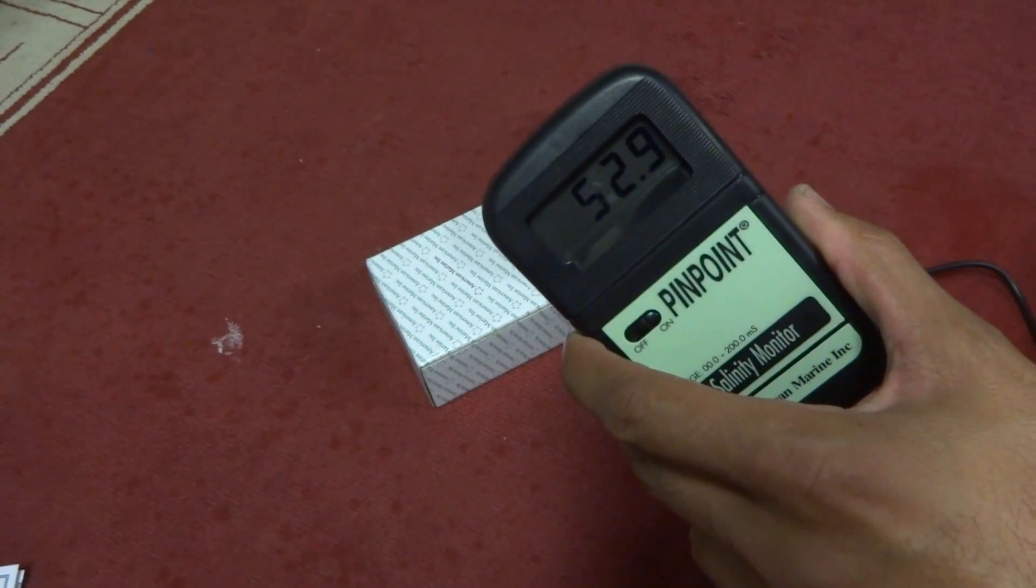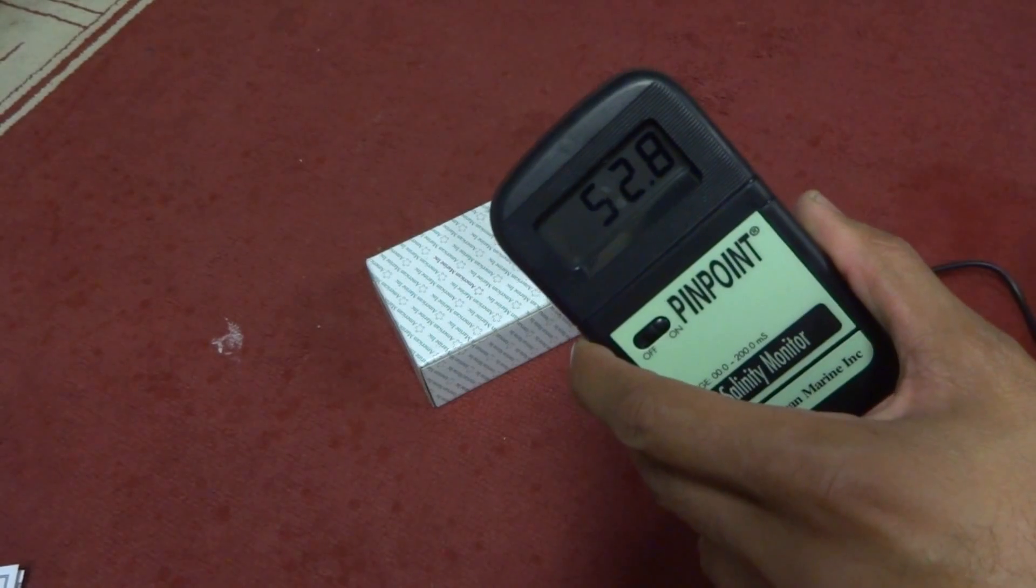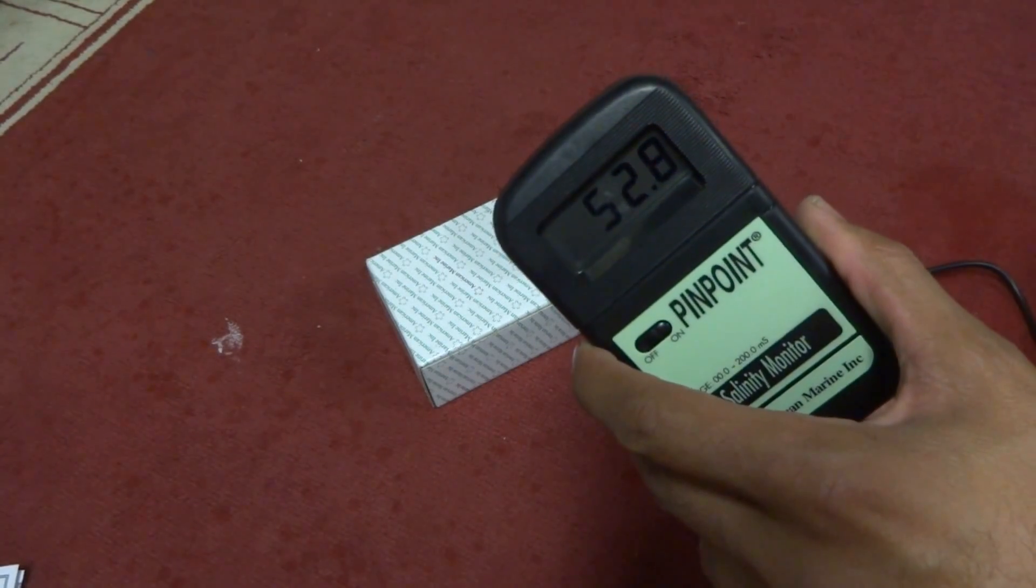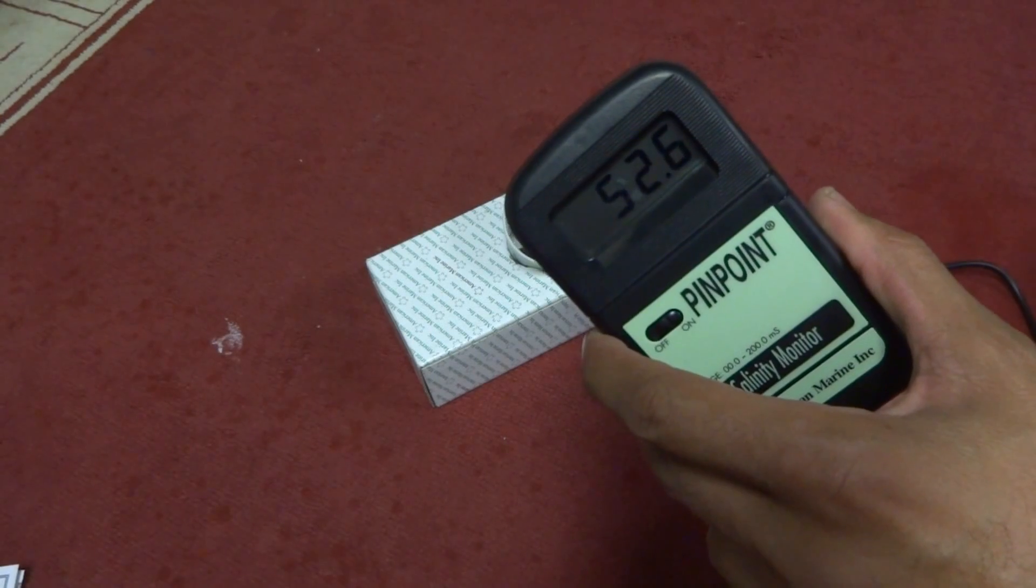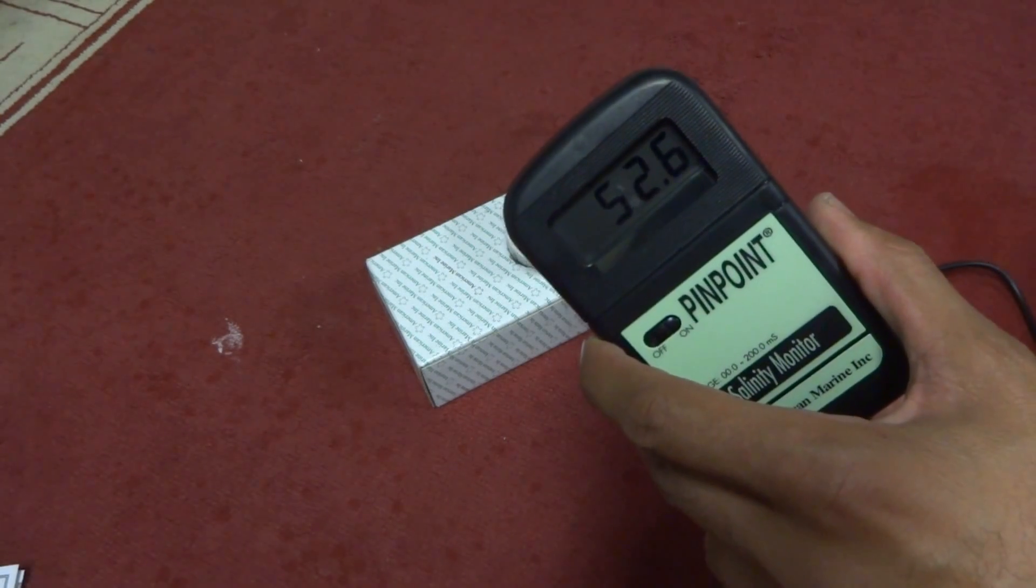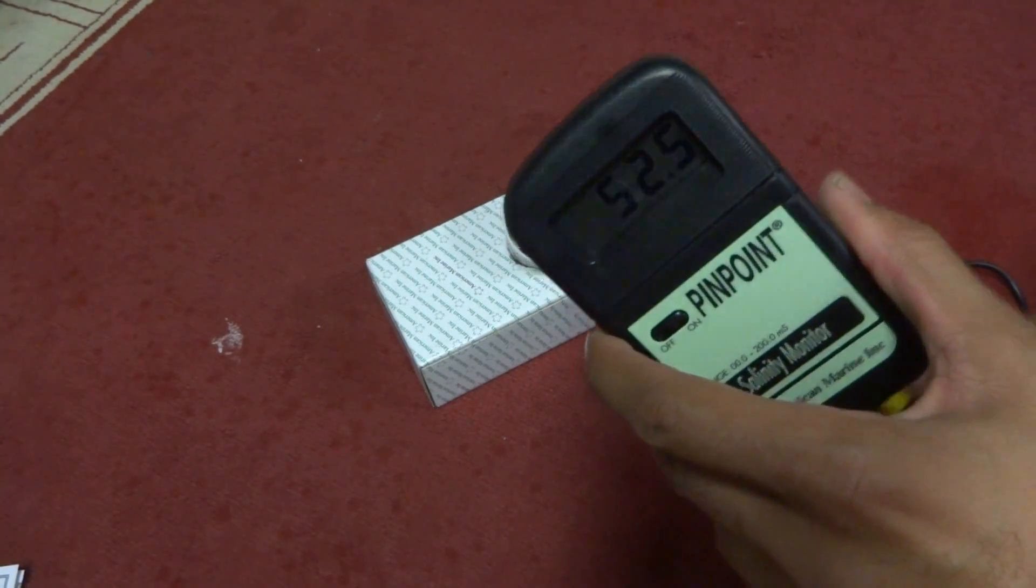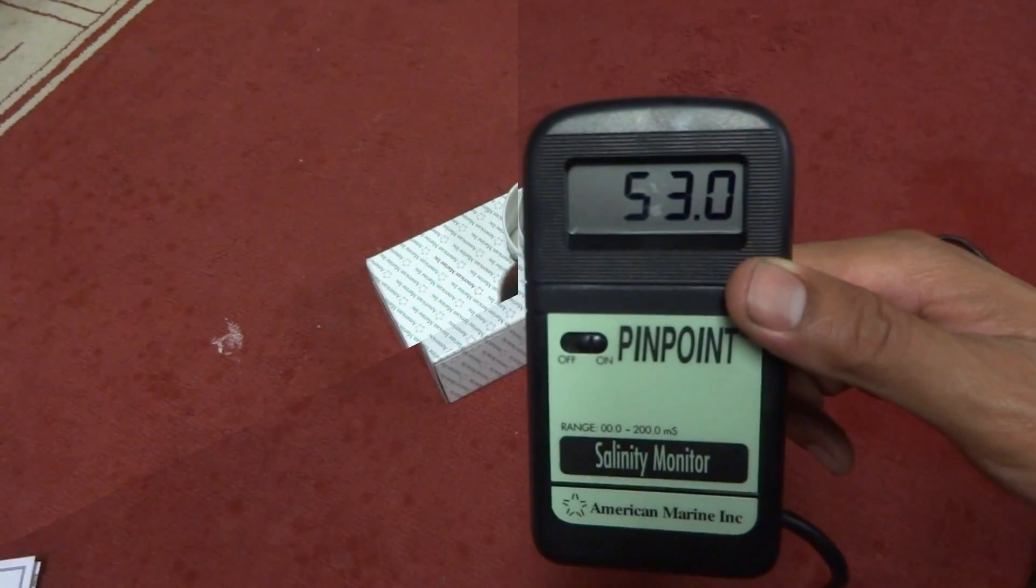And the one thing I didn't mention is when you place the probe into the calibration fluid you want to leave the probe in the fluid for one to two minutes to allow the probe to adjust to the temperature of the calibration fluid itself. And what I'm doing is making very small adjustments to the screw in the back to get this thing to where we want it which is 53.0.